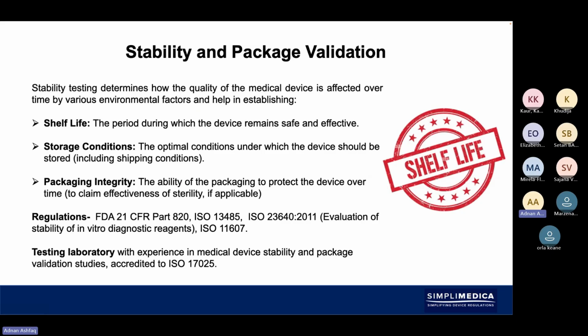If your device is a physical device and not a software medical device, then you need to consider stability in packaging. So there's things like shelf life, storage condition, packaging integrity. You might need to have a look at the sterility. If the product is sterile, you need to make sure that after the shelf life, the device is still sterile and maintains its sterility.